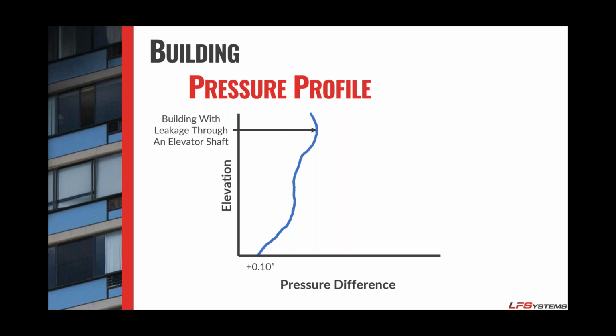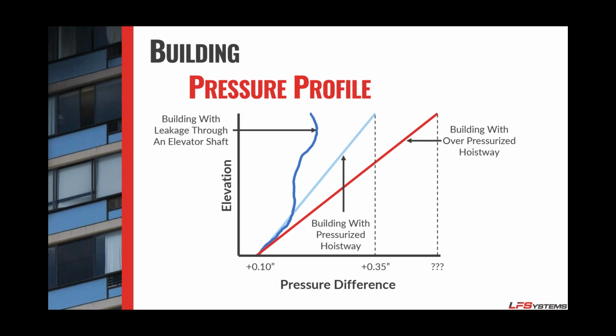And again, your balanced building through the leakage goes away once you pressurize your hoistway, right? It goes back to looking more like this. And by pressurizing the hoistway, you lose the benefit of air movement through the building, which is a good thing because you're now preventing smoke. However, if you overpressurize it, you start to look like this. Too much pressure in the hoistway starts pushing air and smoke back into the corridor, but also back toward the stairwell. So it now affects how your stairwell pressurization system is designed.